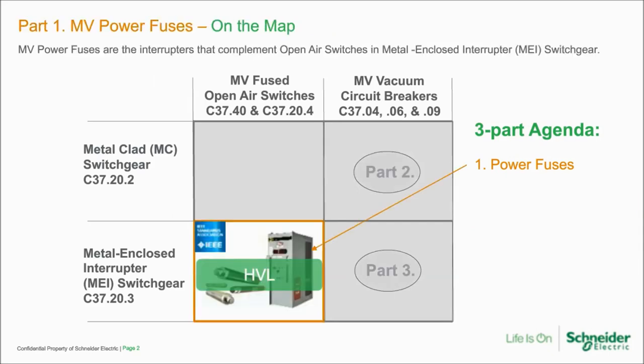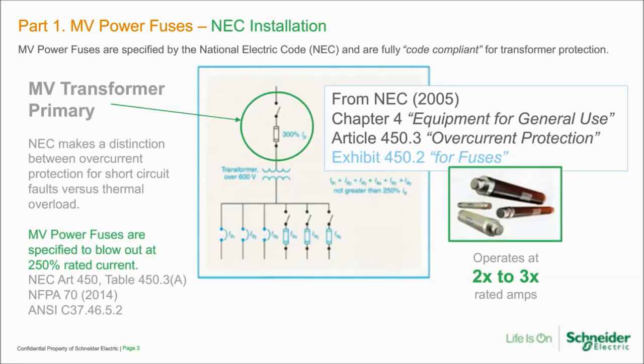Part one: power fuses. MV power fuses are the interrupters that complement open air switches in metal-enclosed interrupter switchgear. We'll be focusing mostly on the application of a transformer primary so that we can compare and contrast the differences. Just realize that the information here is relevant to many other applications as well.